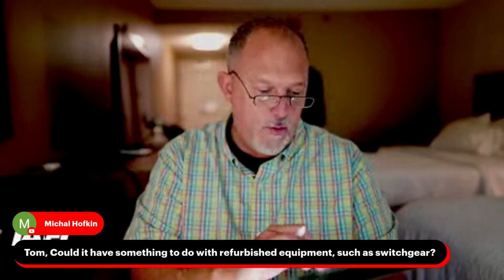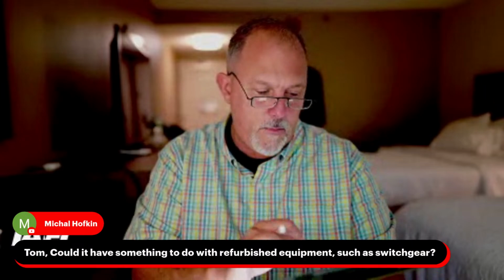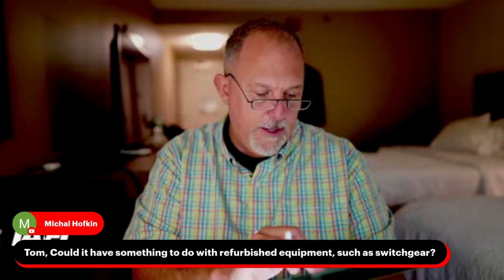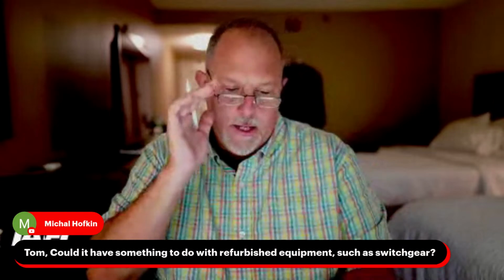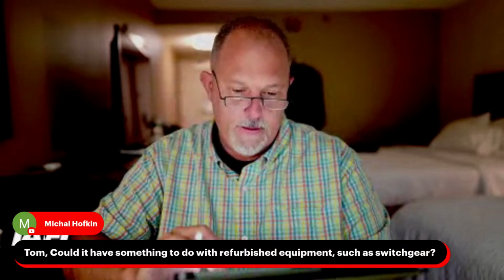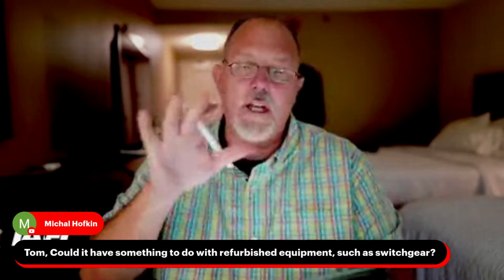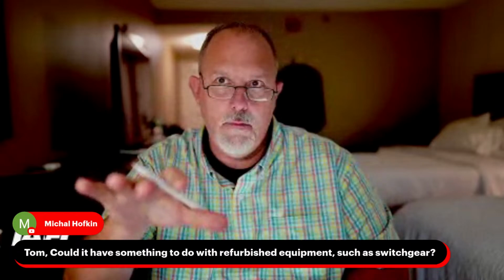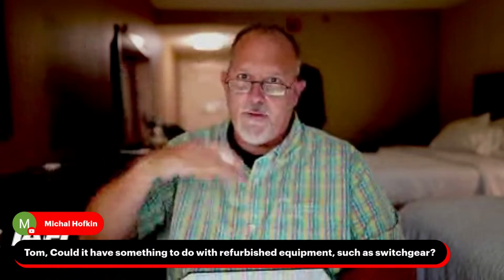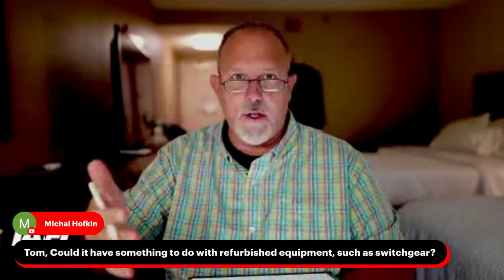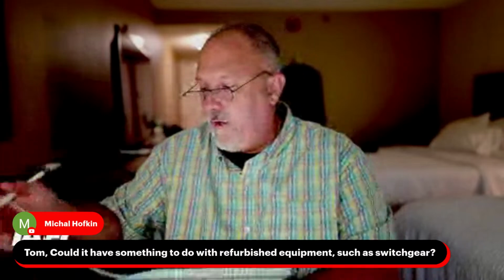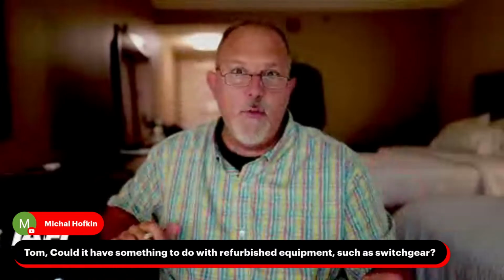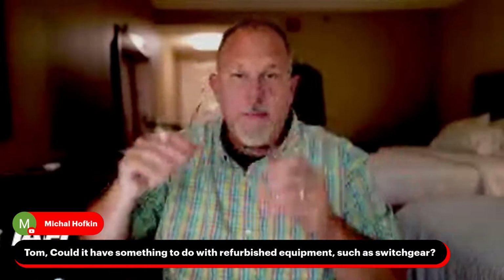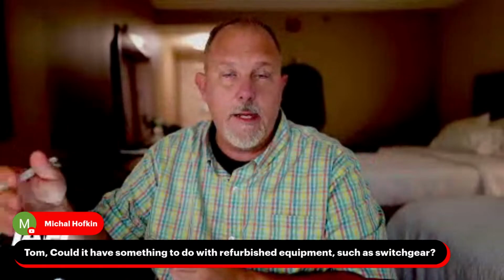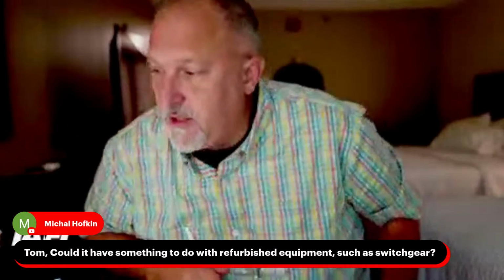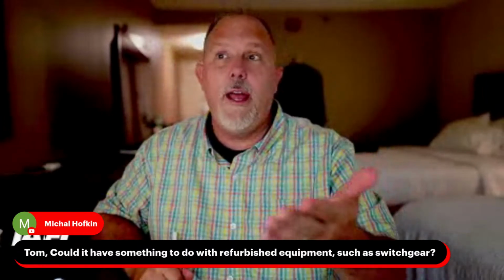I believe you are spot on. When I look at 230 and I look at the listing requirements, we had this discussion that it could be that you have something that was prepared for a utility that's not listed. You have it installed. Now, what do you do? You could do a field evaluation. If you modify the service equipment, I may need to do a field evaluation, right? And remember, a modification could be something as simple, Michael, as changing the label.